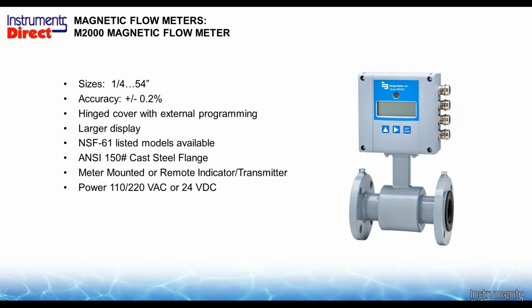The pipe sizes are a plethora of different pipe sizes there, and the adage of cost has dynamically changed in the world of magnetic flow meters in the last 5 or 10 years there. Back when I was a little boy, it used to be $1,000 an inch pipe ID, and now you can buy really big meters for just a few $1,000s. So the price point has really dropped dynamically, and the M2000 and the M5000 are extremely price competitive in the world of magnetic flow meters there. And secondly, if you pick the basic models, they are deliverable usually in about 2 weeks. So you can get a good price and you actually get a delivery for a mag meter. You don't have to wait 4 or 6 weeks and more for something to come over on a boat.